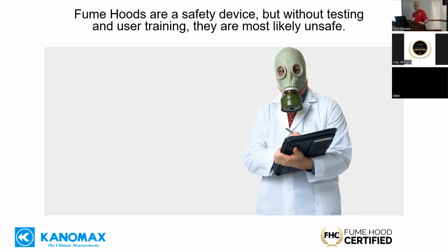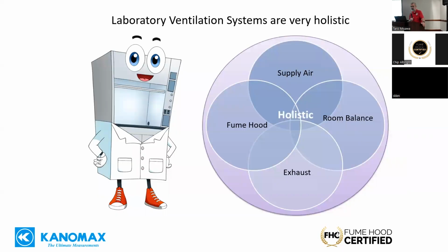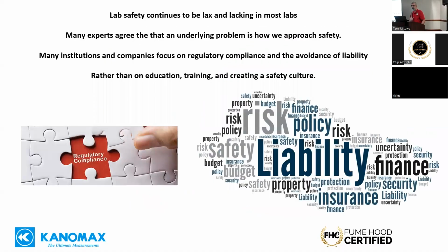So again, the only way we're going to know if your hood works or not is to test it. There's no other way to know. And like I said, laboratory ventilation is very holistic. It's the fume hood, it's the supply air, it's the room balance, and it's the exhaust. And you have to put all those things together in order to have a well-balanced and functional system.